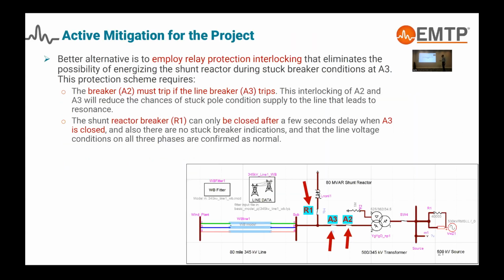And after running this EMT simulation, we also thought about whether there is an active mitigation strategy that we can apply. Because of the configuration of these breakers, we came up with one. The strategy was, when we energize this line, we should energize the shunt reactor after making sure that this line has been energized well, so all the breakers are closed. This was one of the steps. And number two, when we open this line breaker, we will also open this breaker A2, to make sure there is a high probability that both breakers would not malfunction. So it reduces the risk of resonance.